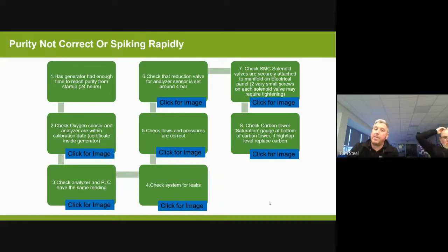The oxygen sensor and analyzer need to be within calibration; the certificate for that is inside the generator. If they're not within the calibration date, you have to look at either recalibrating or replacing. Check the analyzer and PLC have the same reading. What that means is, inside the generator there is a display that shows us what the oxygen content is. There's also one on the output of the generator, on the outside. Make sure they read the same.